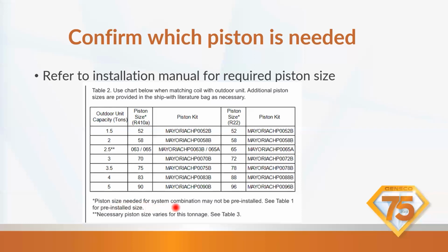Your piston size needed for the system combination may not be pre-installed. It does come with a variety of pistons in there, so hopefully you have the right size piston for what you need. The 3-ton, you're going to need 70, 3.5 ton is 75.